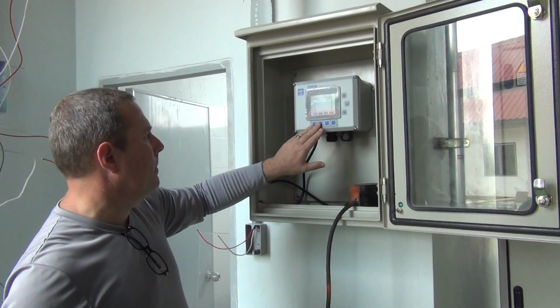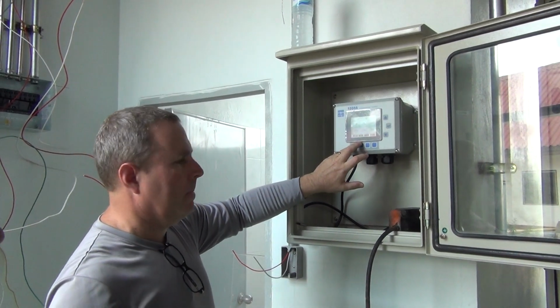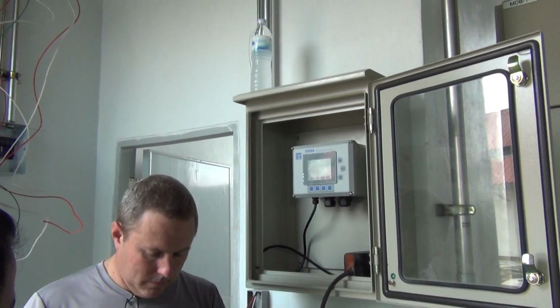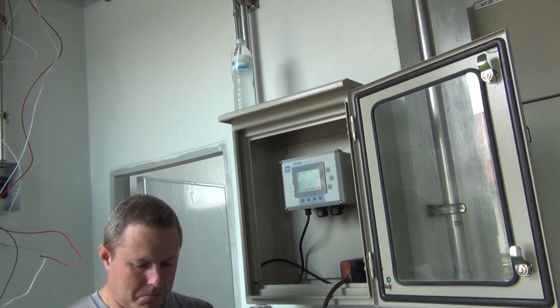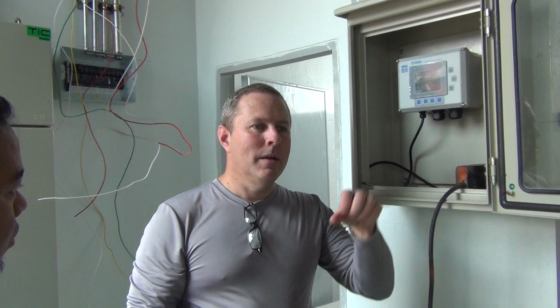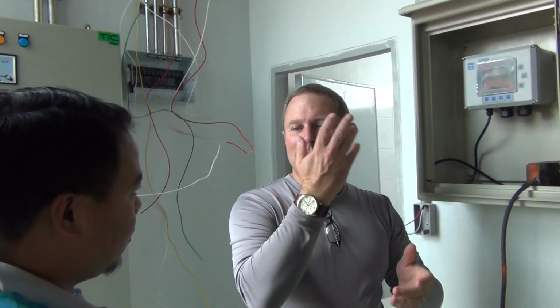Any question? No question. Okay. So let's go back. So, one question here. While cleaning the probe, do we need to disable this service? It is up to you. I don't think that it would be required for what you're doing unless you are calibrating the conductivity, in which case if the pumps were running and you wanted to calibrate the conductivity, what you would not want to happen is you put it into the conductivity solution and then it shuts off all the pumps. Or you're calibrating it and there's salt water and you rinse it with water and it turns on the pumps. Does this make sense? Yes.